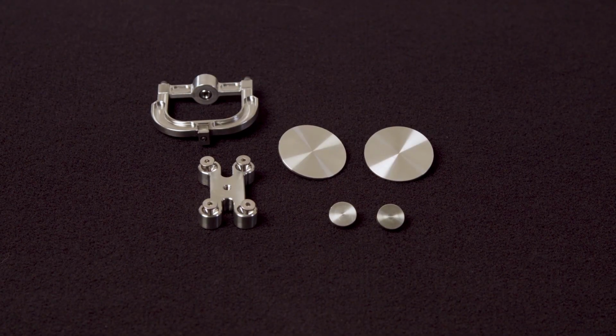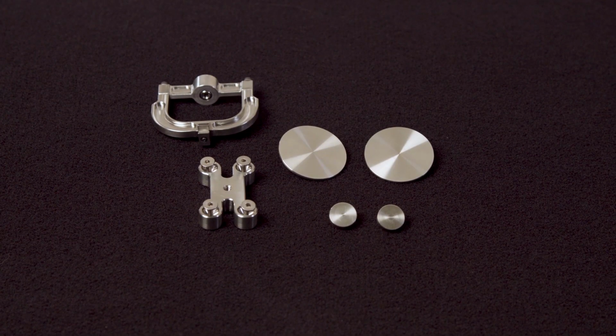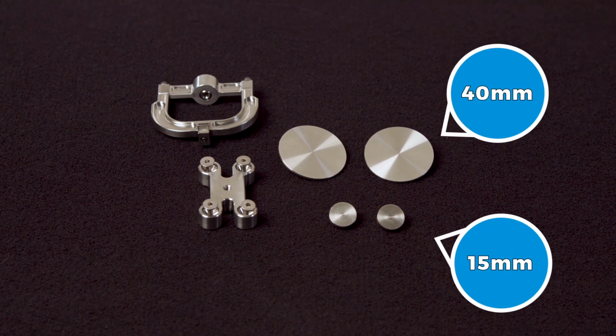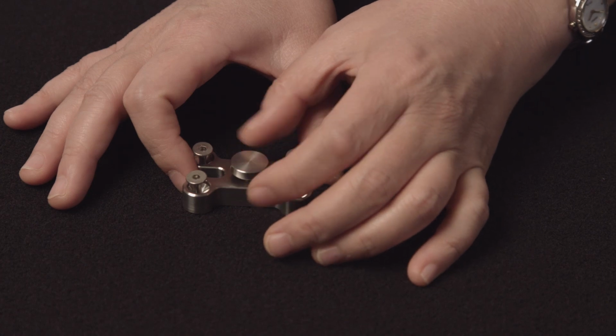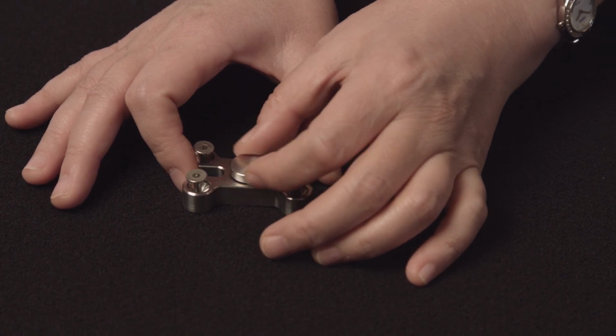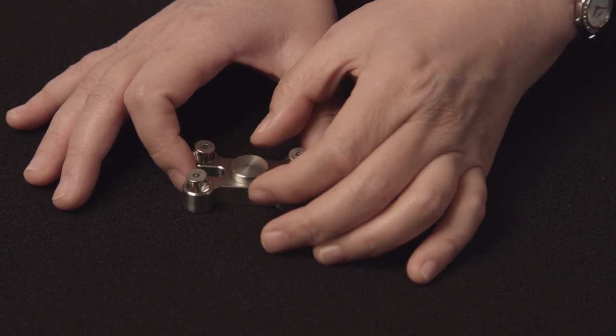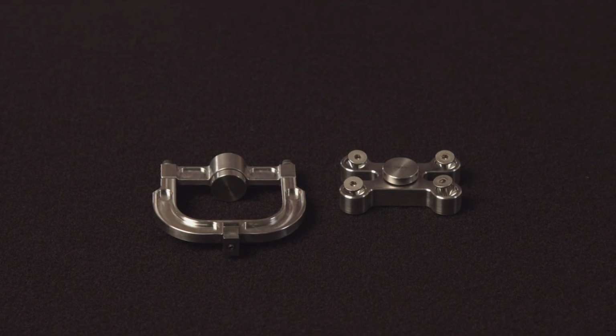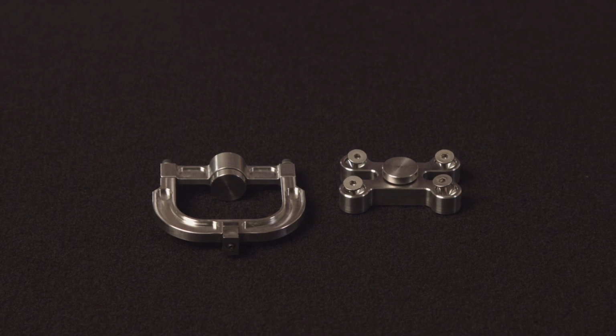In this tech tip, we'll demonstrate how to install and calibrate a compression clamp on a DMA 850. This compression clamp kit has two sets of plates. They are 15mm and 40mm. Depending on the dimension of the sample you need to measure, you can select and attach the appropriate diameter plates to the movable and fixed clamp. For example, we are now attaching the 15mm diameter plate to the clamps for the calibration.